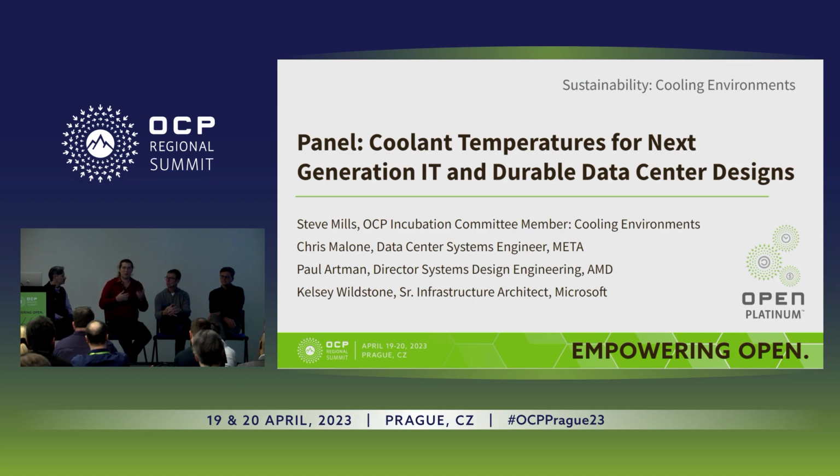if you want to do an efficient data center design, you put in a liquid cooling plant and cycle that facility water through your data center, and you're going to use some of that facility water to turn into air-based cooling, because depending on how you're doing it, you're probably not going to want to install a liquid-cooled facility water plant and then also have an EVAP plant over here with free air. So you could look at it that way and say, even if you're taking some percentage of your liquid cooling load to the data center and turning that into an air mover, the data center perspective from the outside is 100% liquid.